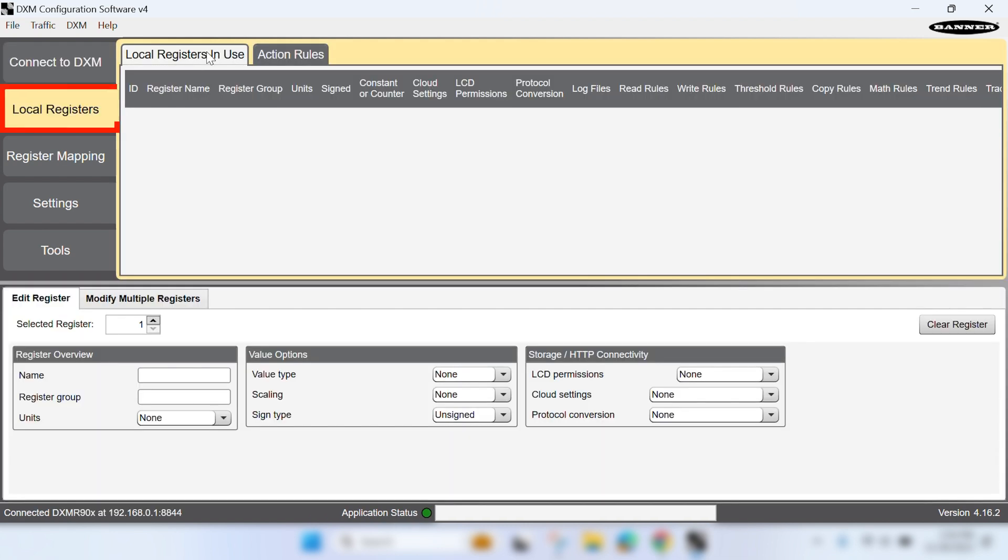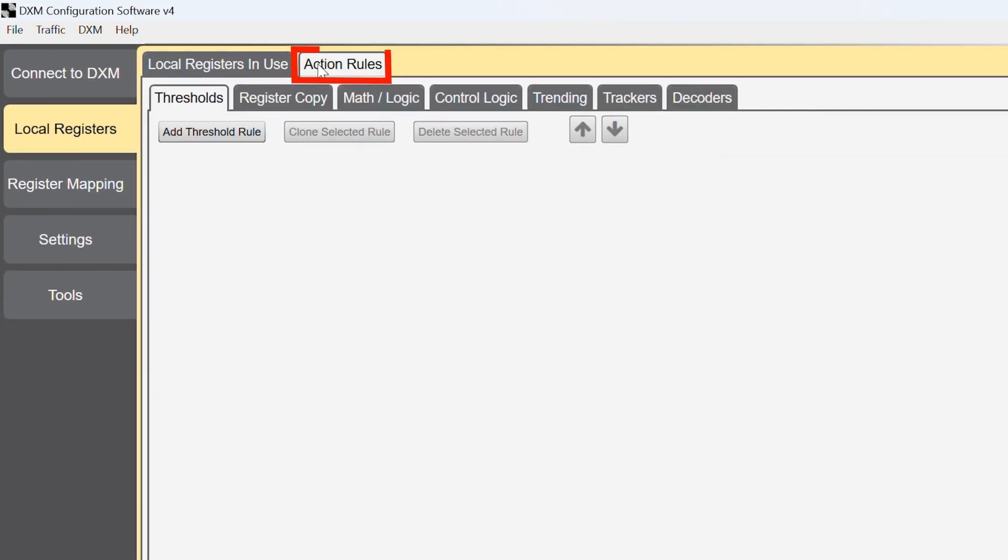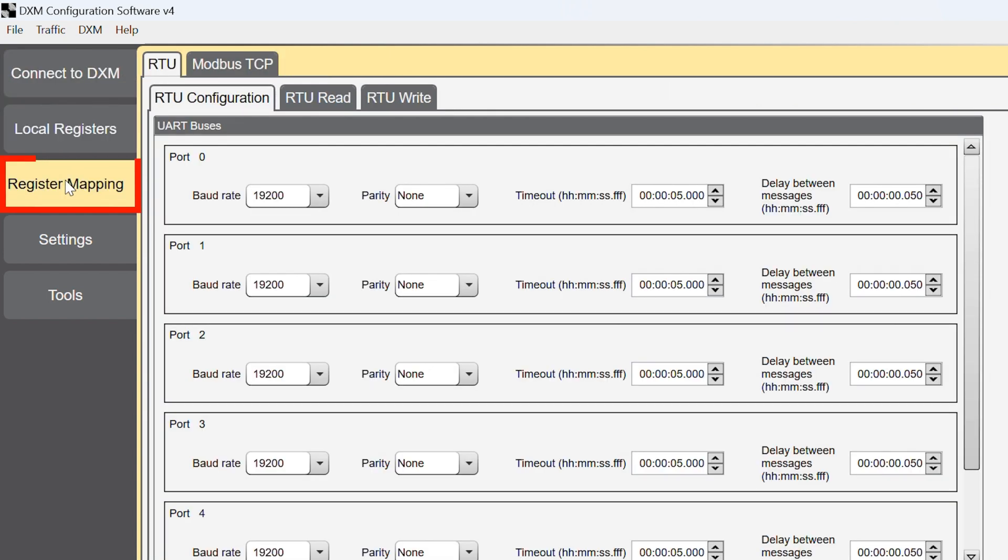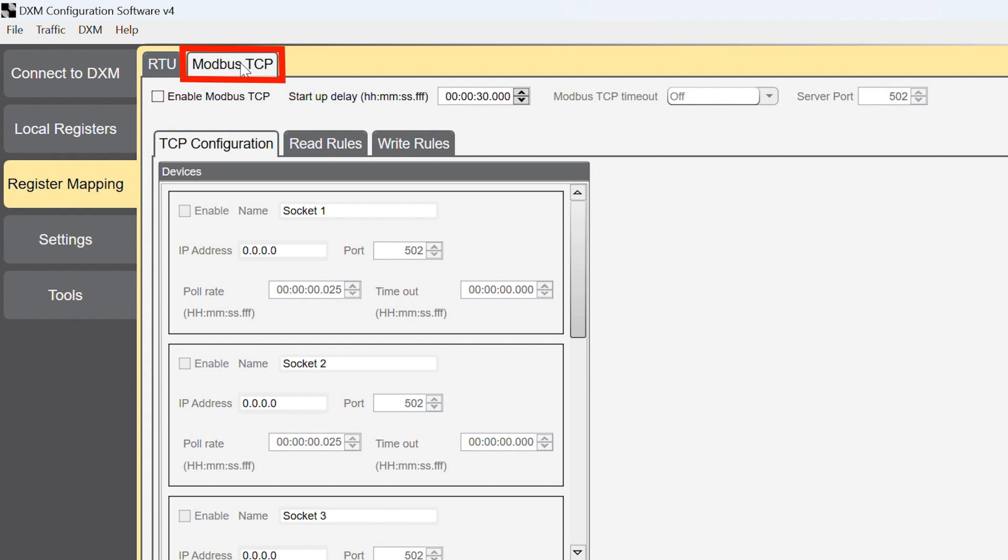In the Local Registers tab, you can modify register settings or add action rules that provide local data processing. Once these are set, you can go to Register Mapping to set your port configurations and then create RTU read and write rules to gather data and configure sensors, or configure Modbus TCP client communications.